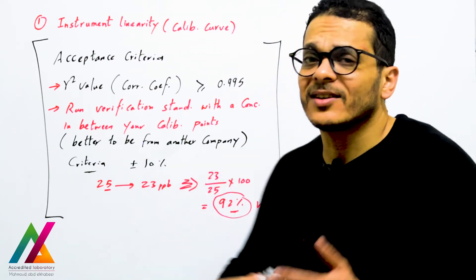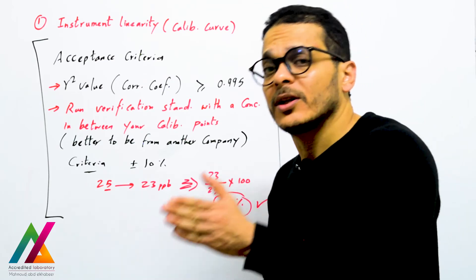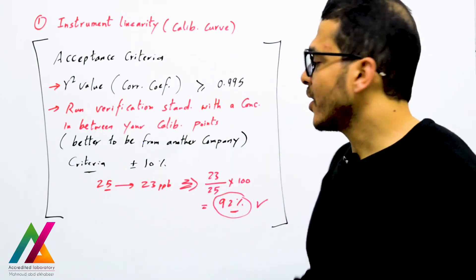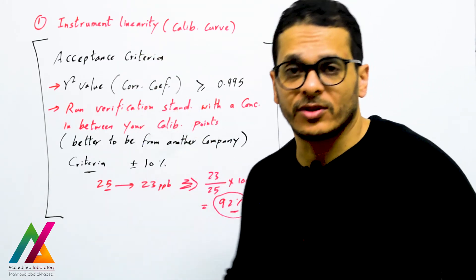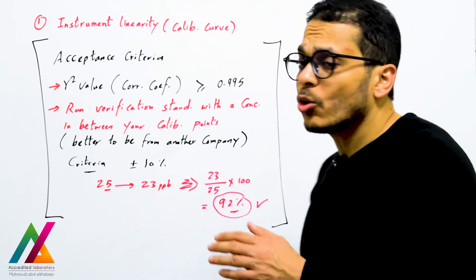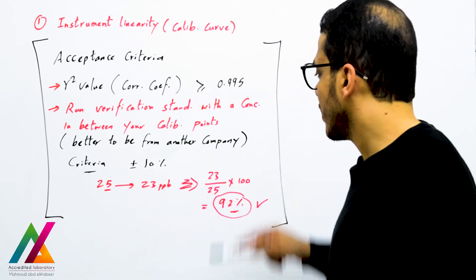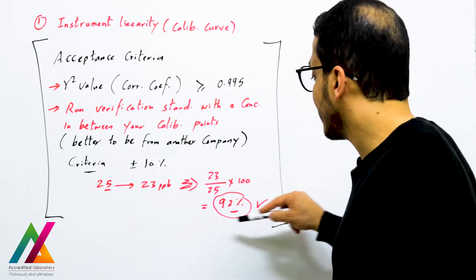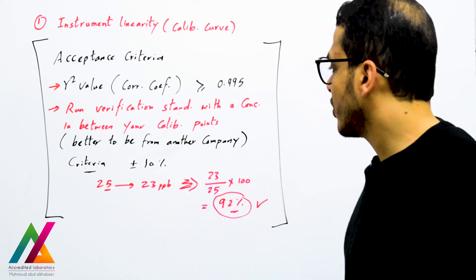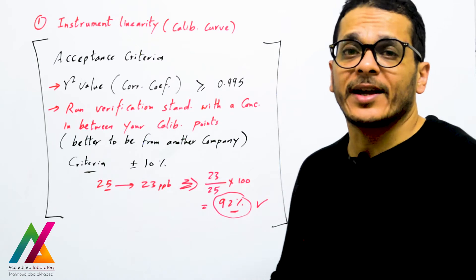The verification standard is preferably from a different company than the one used for calibration standards, though you may use the same source if needed. The acceptance criteria for this standard is ±10% for higher concentrations, and ±20% to ±30% for lower concentrations per some guidelines. For example, running 25 ppb and obtaining 23 ppb gives a recovery of 92%, which is within the ±10% acceptance range of 90–110%, so the calibration curve is accepted.